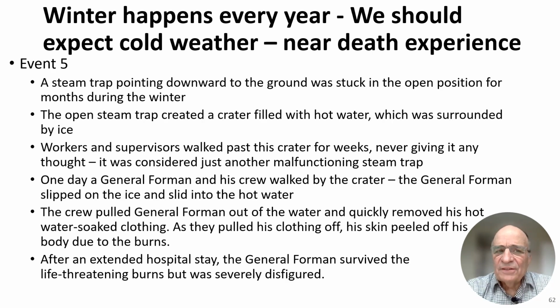Winter happens every year. We should expect cold weather. This is a story about a near-death experience. A steam trap pointing downward to the ground was stuck in the open position for months during winter operation. The open steam trap created a crater filled with hot water, which was surrounded by ice. Workers and supervisors walked past that crater for weeks, never giving it any thought.